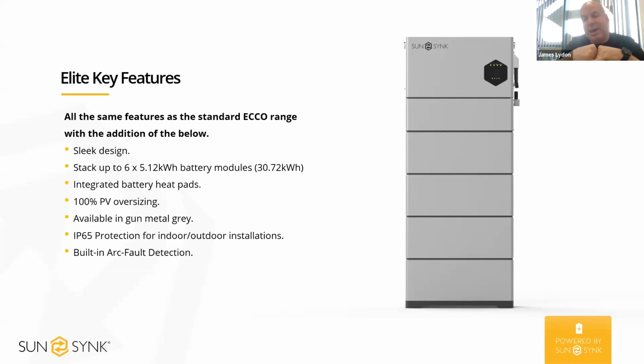The image here shows the base at the bottom. When you're ordering the Elite, there are three SKUs: the inverter size required, the power distribution unit, which comes with the grey base at the bottom, and then however many batteries you need. We also provide adjustable feet for the unit, so they don't need to be used if it's a flat surface, if it's level. But if the installation location is slightly wonky and you need to use the feet, they can be used, and like I say, they can be adjusted either side.